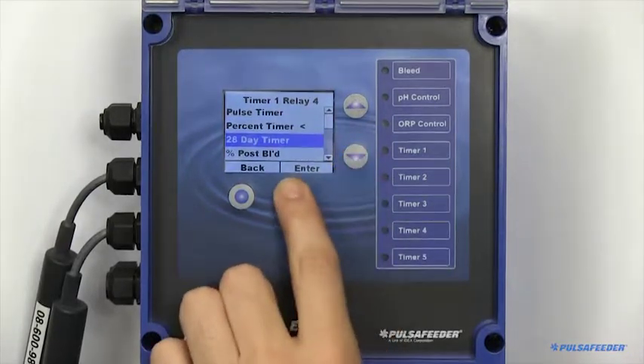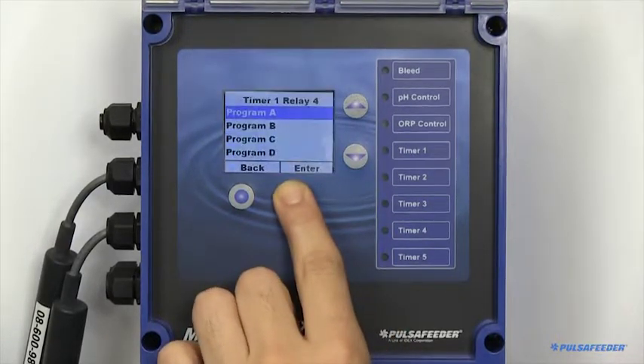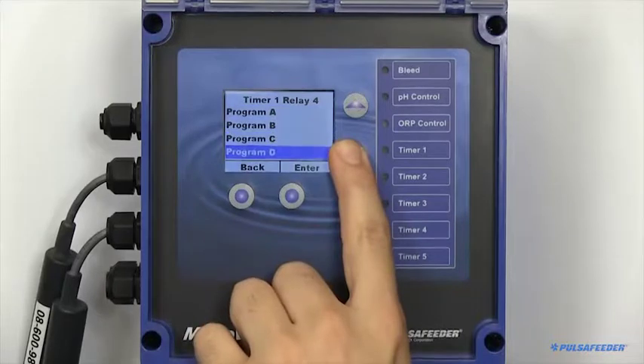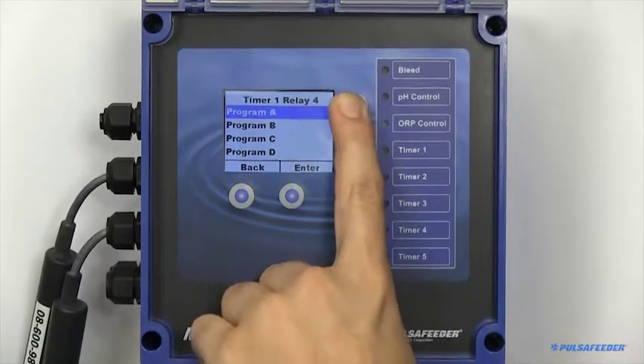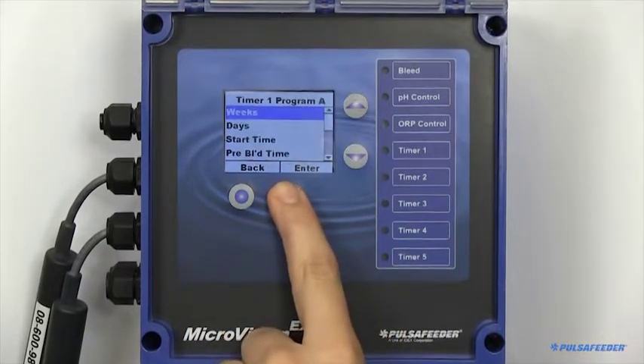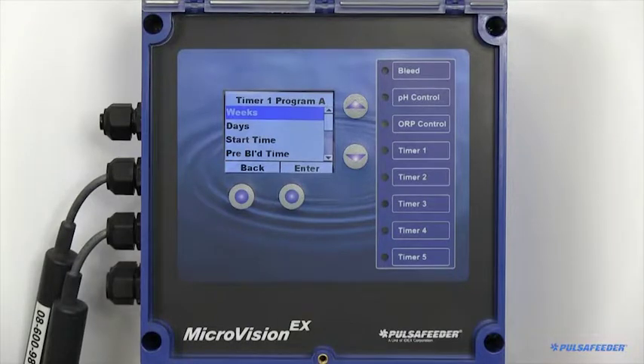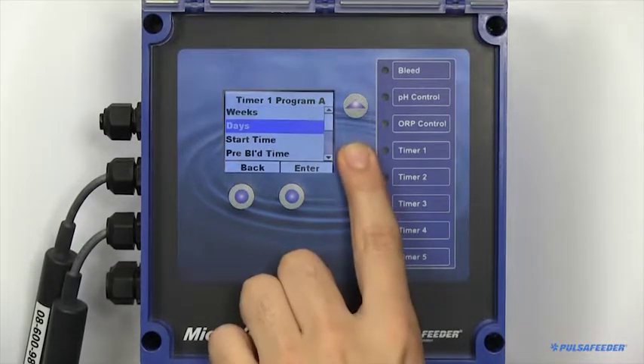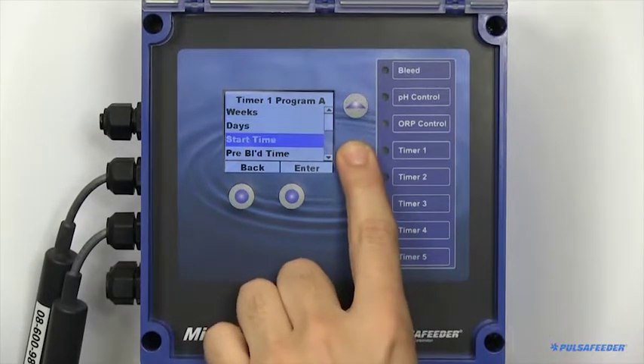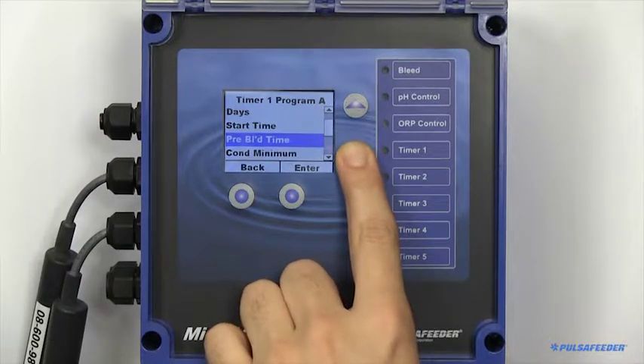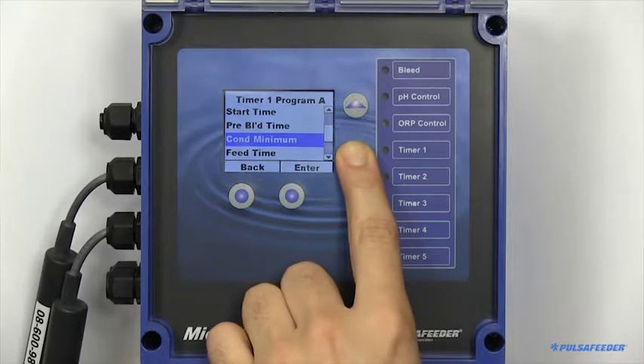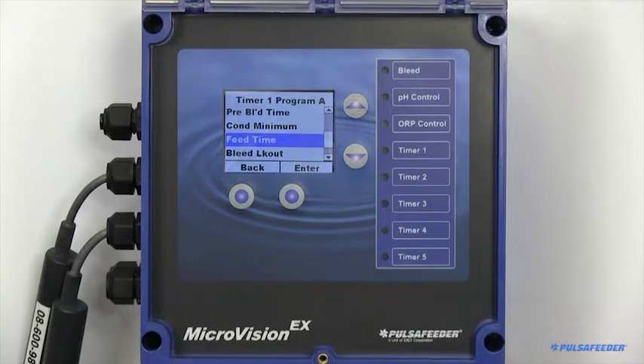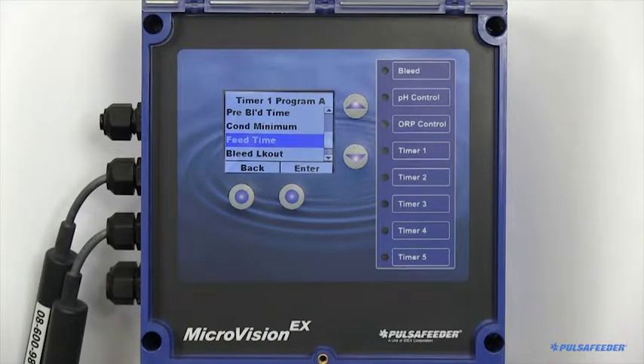A 28 day timer, or biocide, can have four programs running on each relay. To set up a single program of a biocide timer, you need to configure the weeks, days, start time, feed time, and if applicable, specify a prebleed, minimum conductivity, and bleed blockout.